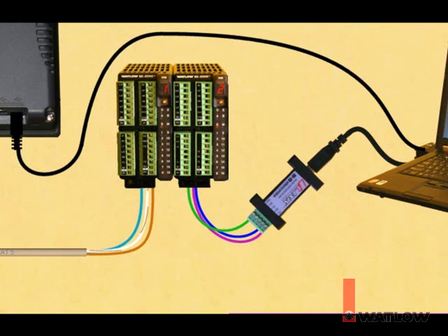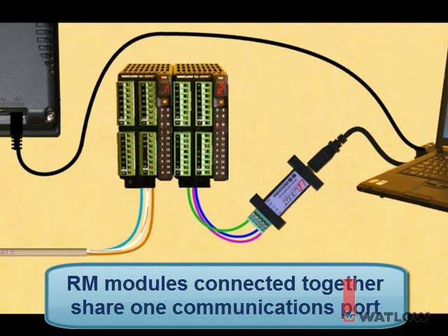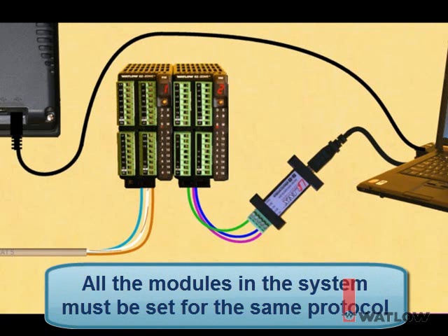There are three important things to note about this network. Though each RM module has its own screw terminals for communications, a group of modules connected together at the backplane share one communications port. So the PC, the OIT, and the control modules connected this way are all on one 485 network. All the modules connected together at their backplanes must be set for the same communications protocol.